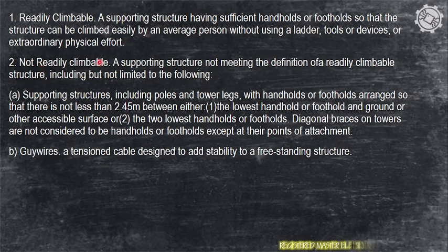Not readily climbable: a supporting structure not meeting the definition above. Including but not limited to supporting structures, including poles or tower legs with handholds or steps so that there is not less than 2.4 meters between either. So ibig sabihin, sobrang layo ng kanyang mga handholds at foot holds. And the other one is guy wires, yung ating support wires na kung saan hindi pwedeng gamitin to climb the structure.